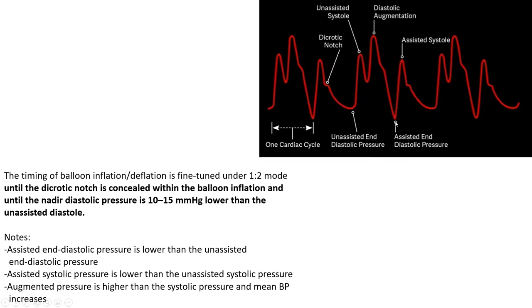Typically, the assisted diastole should dip 10 to 15 millimeters lower than the unassisted diastole, and you should seek that. Same with systole, it should be lower than the unassisted one. And you should not see a dicrotic notch. That's what you verify in 1-2 mode.